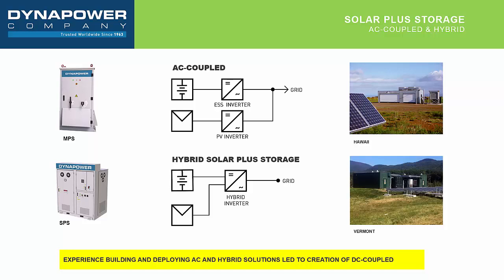However, one of the disadvantages to the hybrid topology, and one of the reasons why it hasn't really taken off as a methodology for solar plus storage, is that once you've designed this inverter, you've designed it with a specific ratio of solar to storage. In the case of the Dynapower designs for hybrid inverters, this is a 1-to-1 ratio. So for every 1 kilowatt input of solar, you have 1 kilowatt input of storage. And the problem there is that you lose design flexibility. Many solar plus storage systems today are not built around a 1-to-1 ratio of power from the solar and the storage. And so you lose that flexibility if you wed yourself to the hybrid inverter topology.